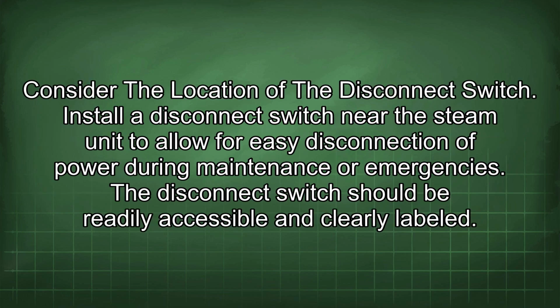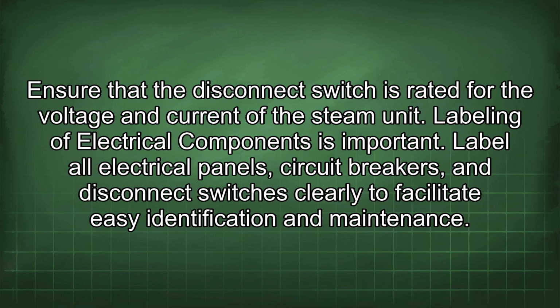Consider the location of the disconnect switch. Install a disconnect switch near the steam unit to allow for easy disconnection of power during maintenance or emergencies. The disconnect switch should be readily accessible and clearly labeled. Ensure that the disconnect switch is rated for the voltage and current of the steam unit.